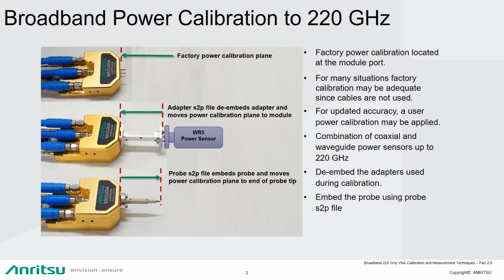So before talking about the full probe calibration process and options that we have, I thought it'd be first good to discuss the power calibration aspect of a broadband system. Now, typically what you would be getting from a broadband system is a factory power calibration at the millimeter wave module test port, and that is what we do with the 220 GHz system. So there is a factory power calibration at the module plane.